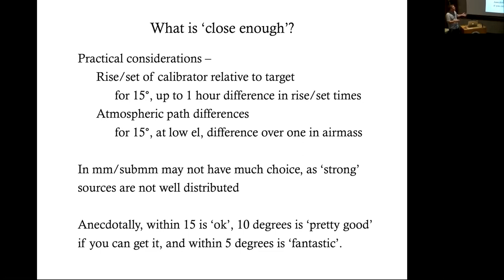So yes, be closer if you can, but as we've already said, you might not have a whole lot of choice. Anecdotally, if you have to go to 15 degrees separation, it will work. We've gone more than that, even 20 to 25 degrees if needed, but hopefully you don't have to. Within 5 degrees is typically the case where you say, wow, you picked the right source, right close to a calibrator. Actually, the best case is if you can make your source itself a calibrator, but we'll get to that.